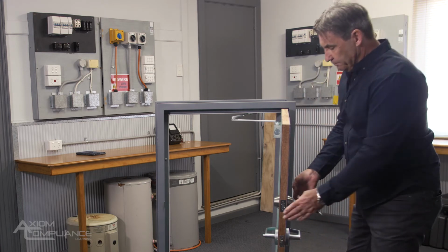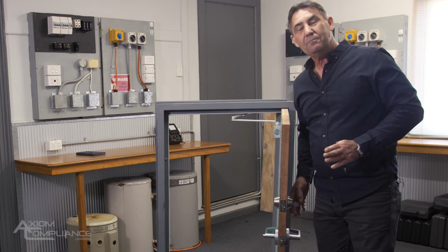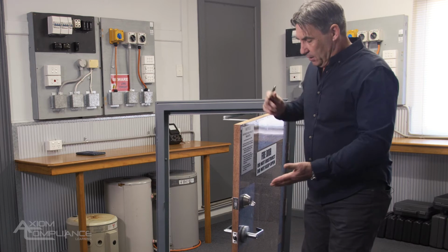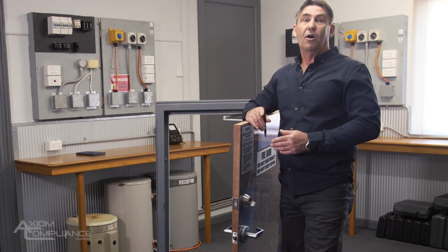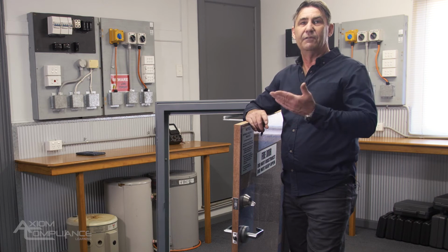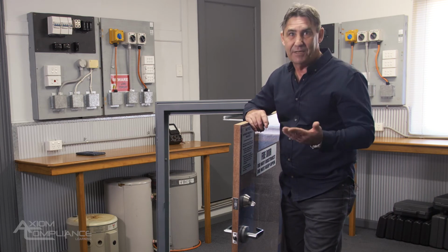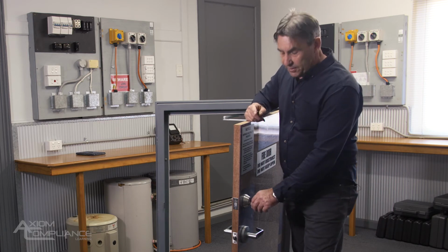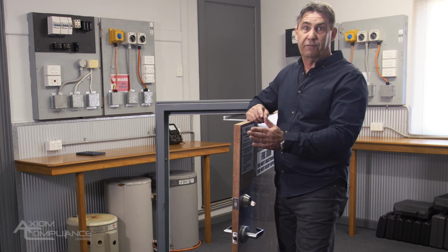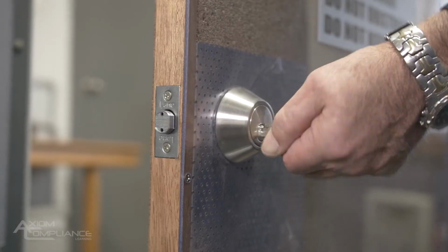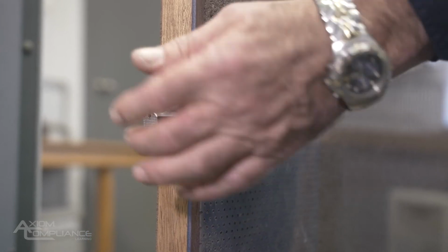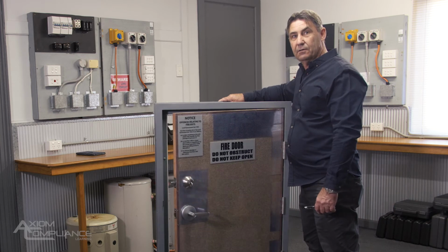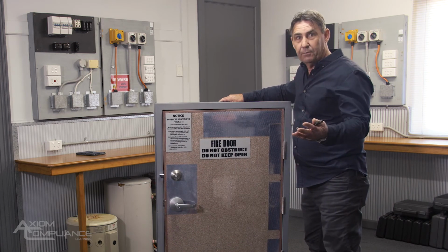Now I'm looking at the lock. Now, a fire door should not be able to be locked. The only time a fire door can be locked is if it's a part of a living quarters or living unit, which makes sense. You've got to be able to provide security for yourself and your family. So there are conditions though. If I'm going to put a lock on a fire door, it can't be a deadlock, because a deadlock will prevent the door from closing. And it's no longer a fire door anymore.